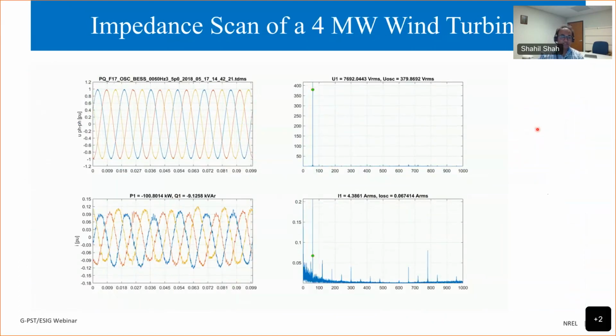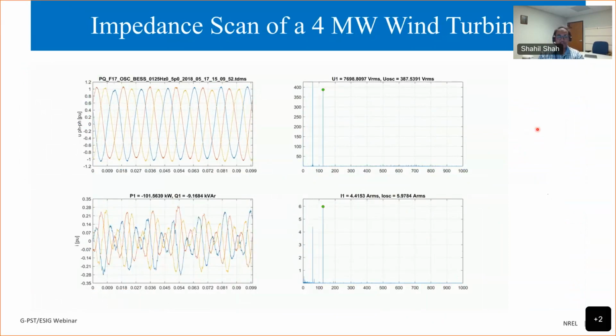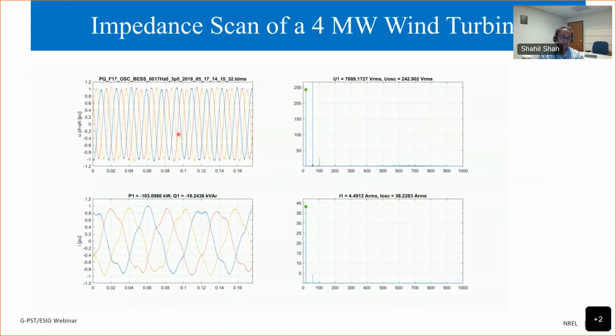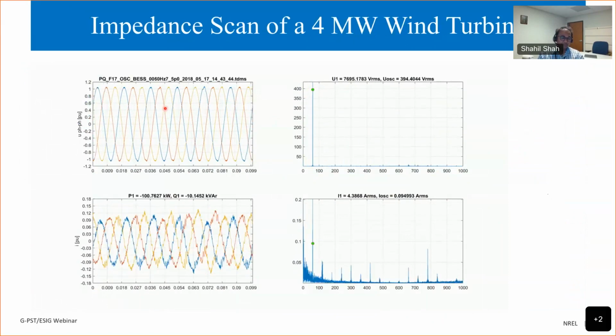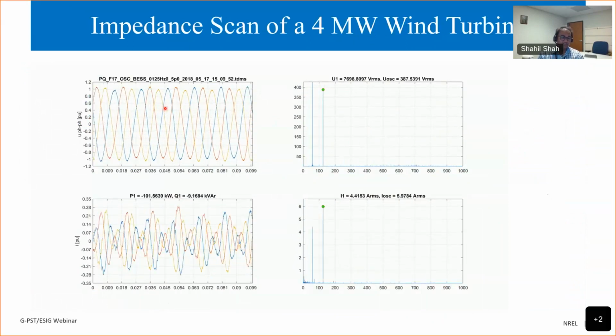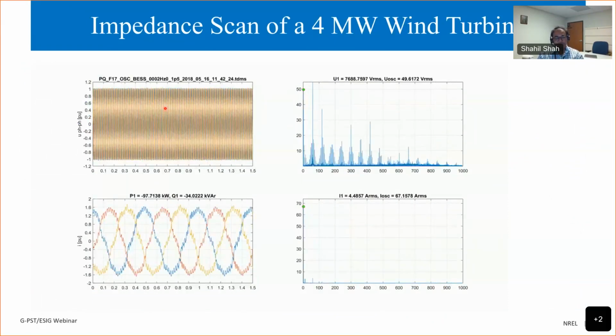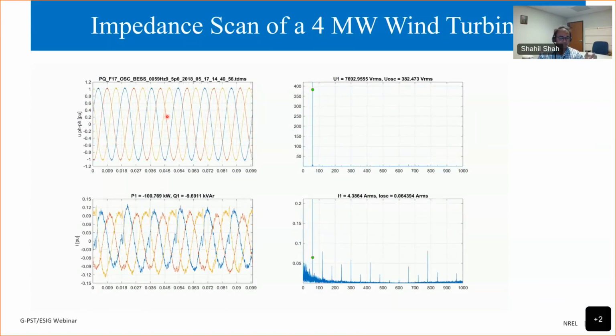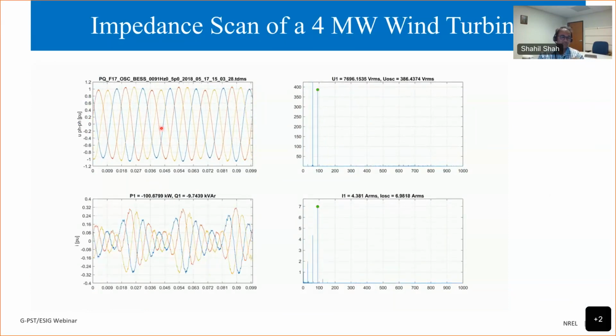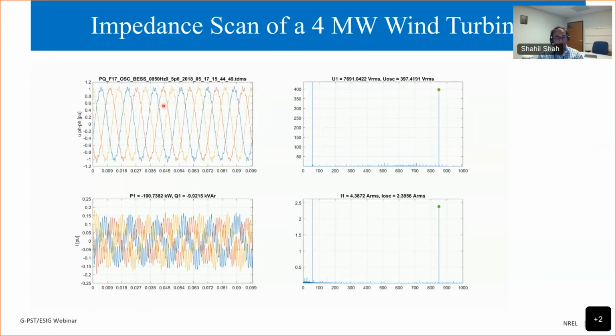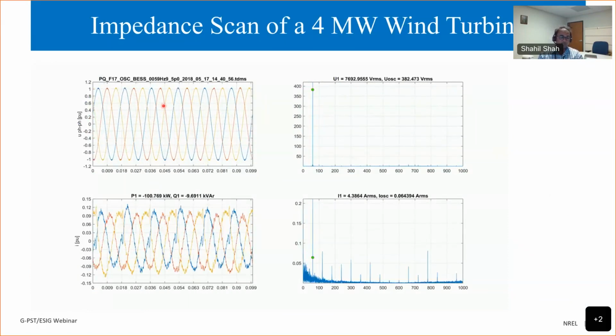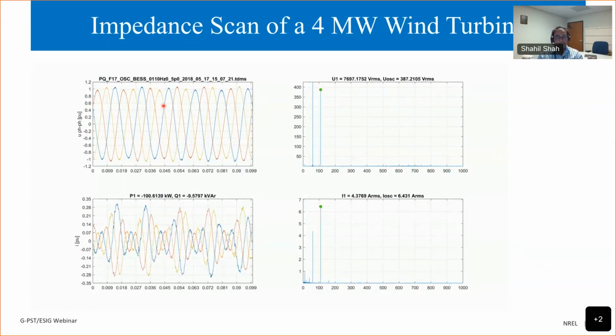This is the impedance scan in action, or basically how it happens for a 4 megawatt turbine. So top left is three-phase voltages at 13.8 kV level, which are imposed on the turbine. And the grid simulator includes not just the fundamental voltages, but also the high frequency perturbations, which go from 0.1 hertz to a couple of kilohertz.